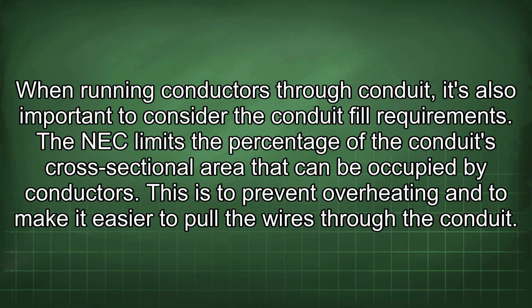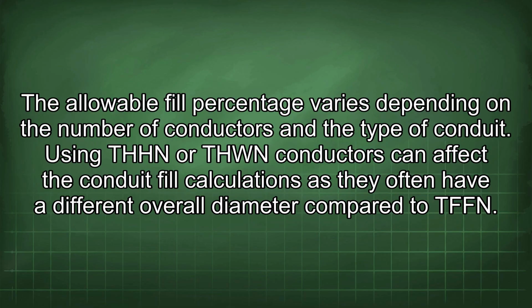When running conductors through conduit, it's also important to consider the conduit fill requirements. The NEC limits the percentage of the conduit's cross-sectional area that can be occupied by conductors. This is to prevent overheating and to make it easier to pull the wires through the conduit. The allowable fill percentage varies depending on the number of conductors and the type of conduit.